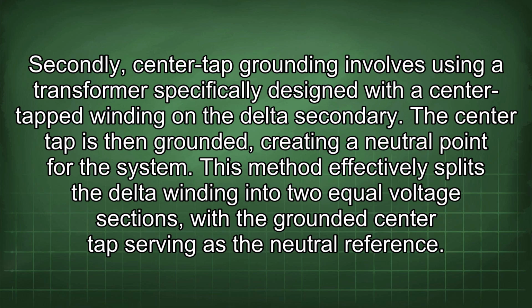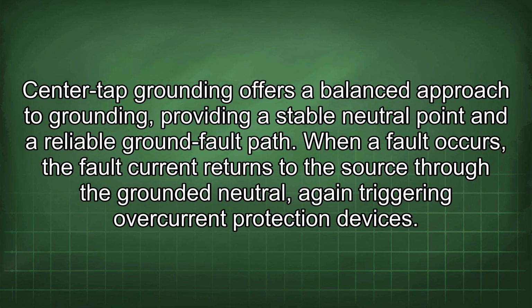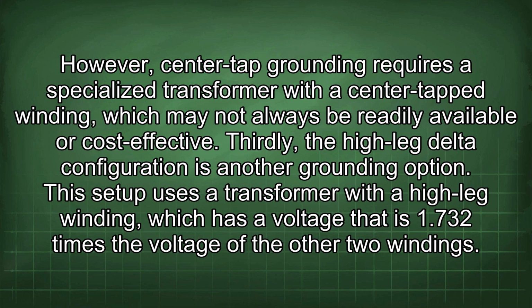Secondly, center tap grounding involves using a transformer specifically designed with a center tapped winding on the delta secondary. The center tap is then grounded, creating a neutral point for the system. This method effectively splits the delta winding into two equal voltage sections, with the grounded center tap serving as the neutral reference. Center tap grounding offers a balanced approach to grounding, providing a stable neutral point and a reliable ground fault path. When a fault occurs, the fault current returns to the source through the grounded neutral, again triggering overcurrent protection devices. However, center tap grounding requires a specialized transformer with a center tapped winding, which may not always be readily available or cost-effective.